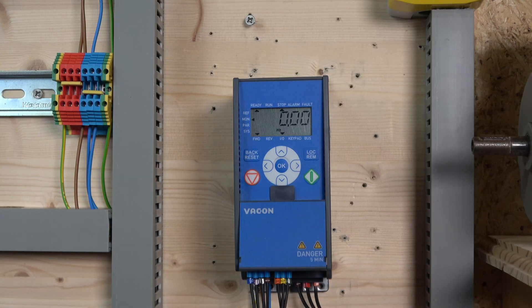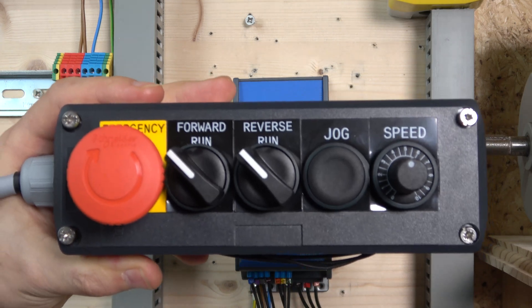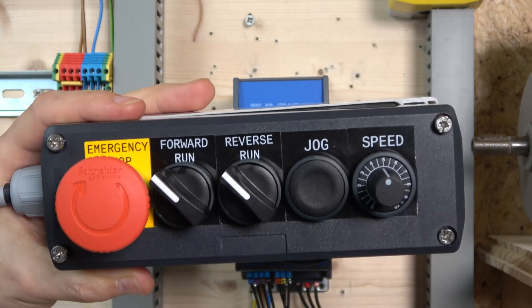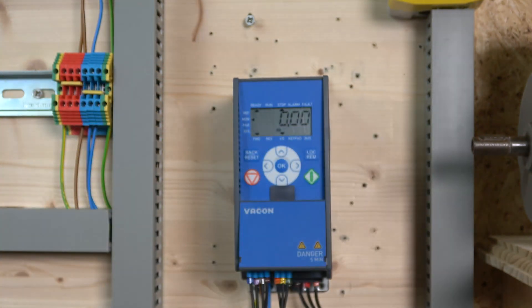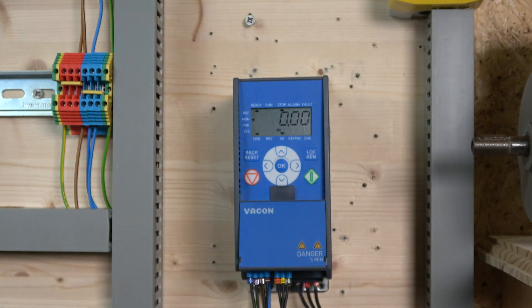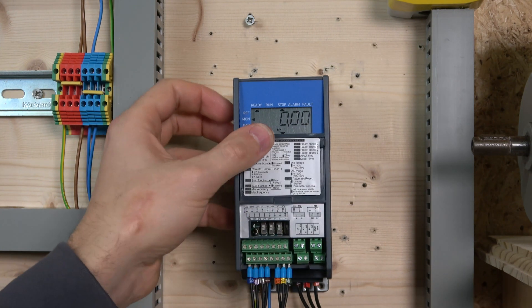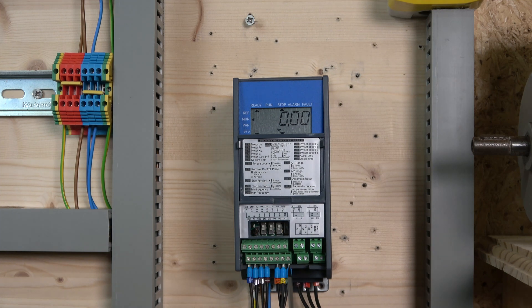Our first station will have run-forward, run-reverse, jog, and we'll be using a remote potentiometer rated from 1 to 10 kilohm. The three cables from the potentiometer go into terminals one, two, and three.